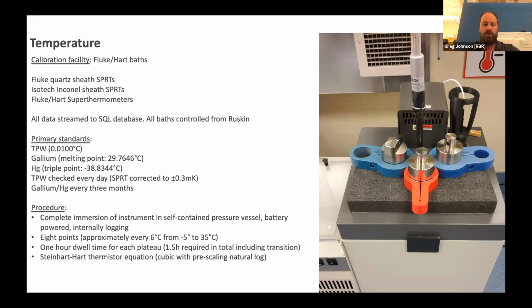I mentioned and showed you some of those primary standards that we use. There are many primary standards, which are materials with intrinsic temperature stability for either a solidification, or usually it's actually the melt point that's used for gallium. The solidification point's a bit complex to determine. Or triple points. And so the triple point of water has this amazing number that you would think is made up. And I don't know enough about ITS 90 to tell you really why it's 0.01000. But obviously the triple point is a much more stable physical parameter than the melting or boiling point. So we use that as much as possible.